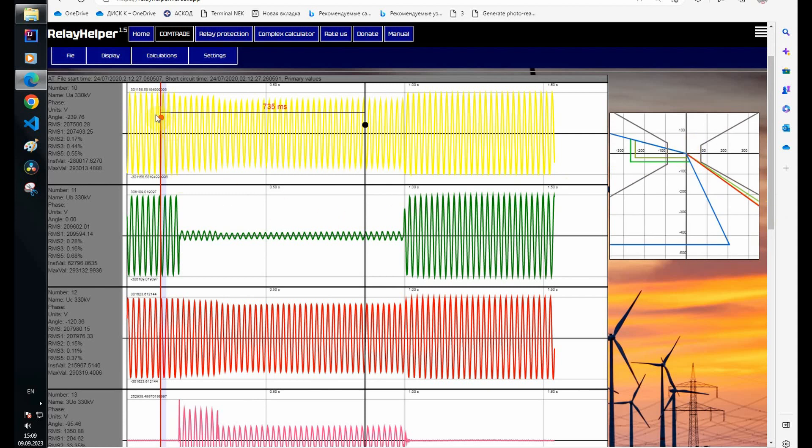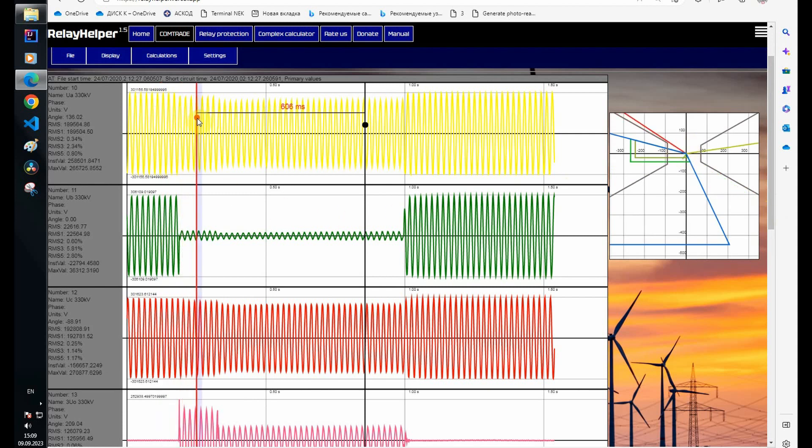Let's look at the section with a short circuit until the moment of disconnection from the opposite side. The short circuit impedance falls into the second and third zones and we should see starts of these zones in digital channels.